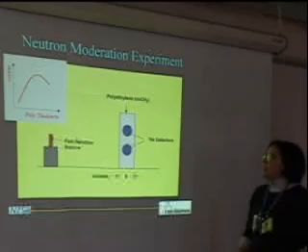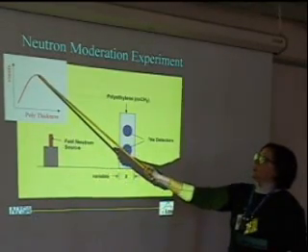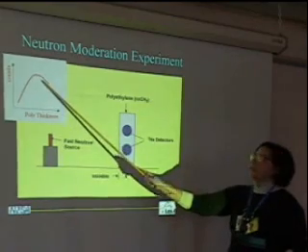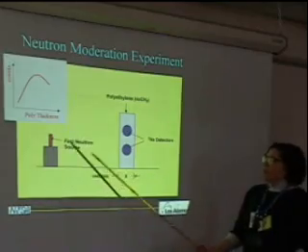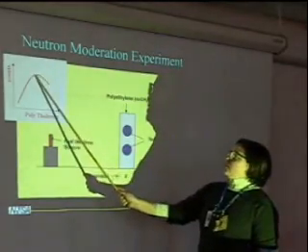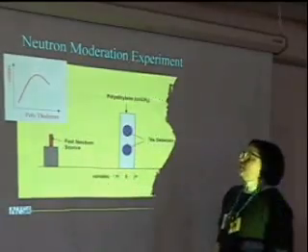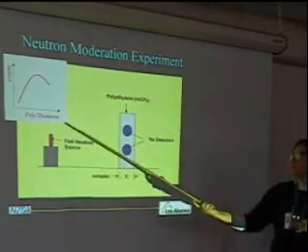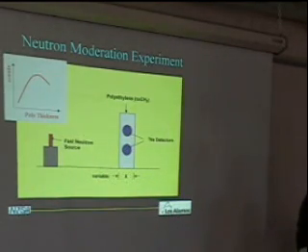And you find that at some point it reaches a maximum, and then you start losing neutrons, and it starts to come down again. So the typical detector is actually slightly under-moderated, because you can always add moderation, and you can also have moderation in a sample that you're interested in, so it's better to under-moderate than to over-moderate.